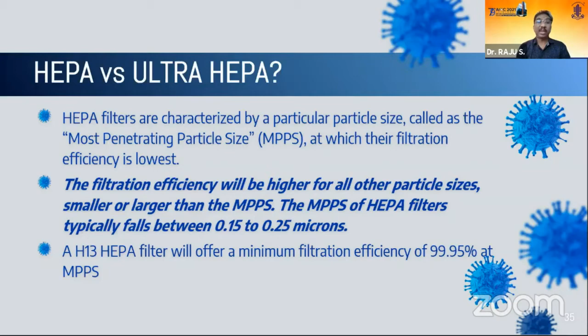Then the next question was HEPA versus ultra HEPA. So this was also making the rounds when we were discussing last year. Again, it's very important to understand the concept of most penetrating particle size. The filtration efficiency will be higher for all particle sizes, either smaller or larger than the most penetrating particle size. The most penetrating particle size for HEPA filters typically falls between 0.15 to 0.25 microns. So anything smaller than this will also be filtered efficiently by the HEPA filter. That is very important to understand, and this is the concept of the most penetrating particle size.